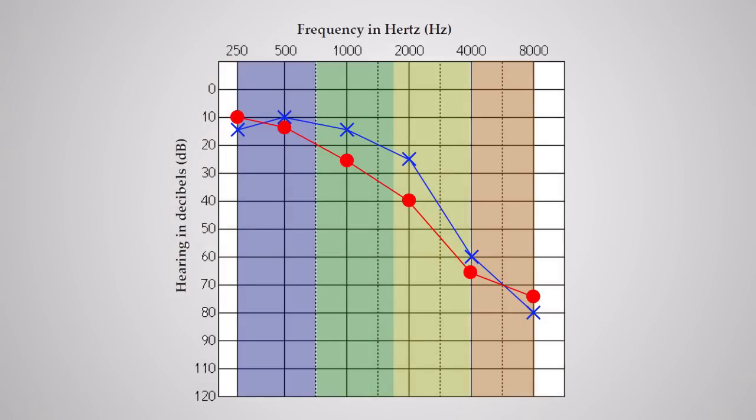For example, an aid with 4 channels might be set up as follows. Channel number 1, 250 Hz to 750 Hz. Channel number 2, 750 Hz to 1,750 Hz. Channel number 3, 1,750 Hz to 4,000 Hz. Channel number 4, 4,000 Hz to 8,000 Hz.